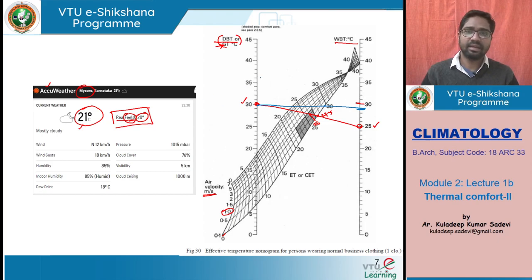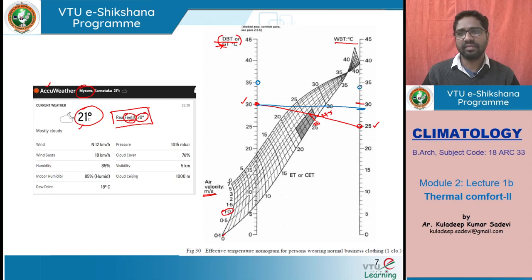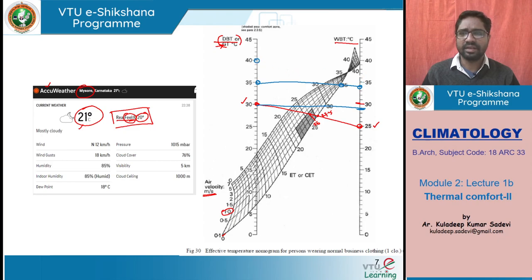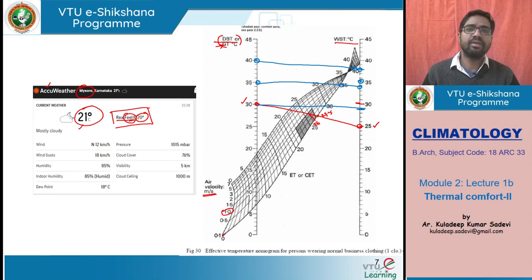Let us say if the outdoor reading is 35 degrees centigrade and it is an over-humid place with higher humidity, and the wet bulb temperature reading is around 34 degrees centigrade — joining these, the actual feeling goes to 35 degrees centigrade. But if it goes beyond this, say 40 degrees centigrade, it will drastically differ. For example, if the dry bulb temperature is 40 degrees and wet bulb is 38 degrees, joining these two, your feeling is beyond or near 40 degrees centigrade. So based on dry bulb, wet bulb, and velocity, your comfort levels keep varying.